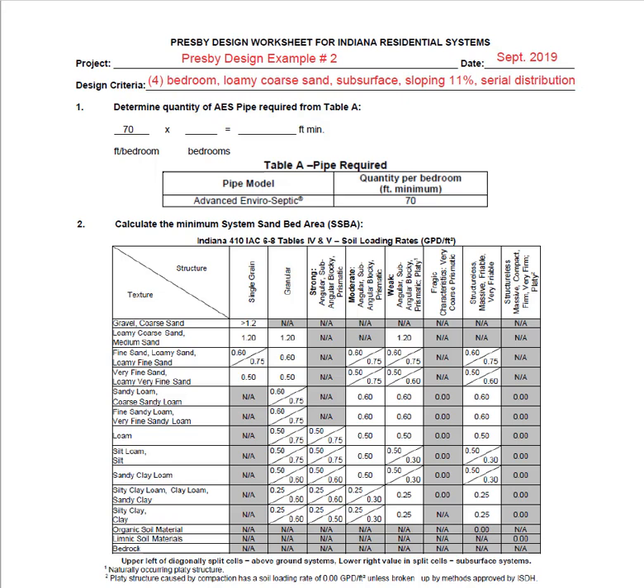Step number one is to determine how much Advanced Enviro-Septic pipe is required. As you can see looking at table A, 70 feet of pipe per bedroom is standard. We will enter our number of bedrooms — in this case four — and multiply by 70 feet. This brings us to a total of 280 feet of pipe minimum.